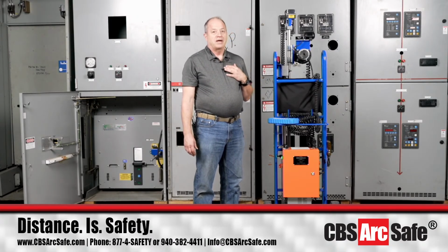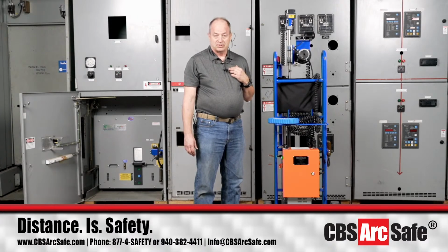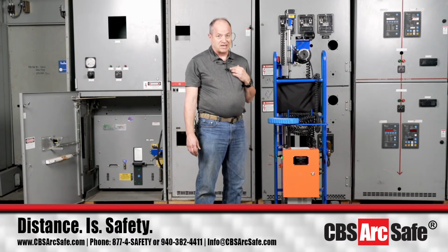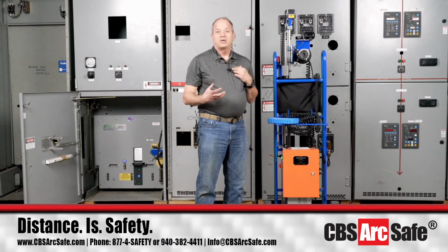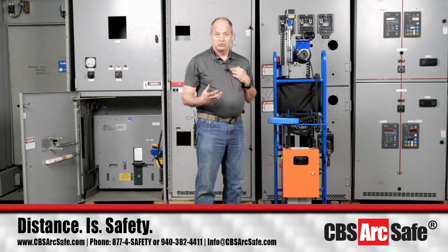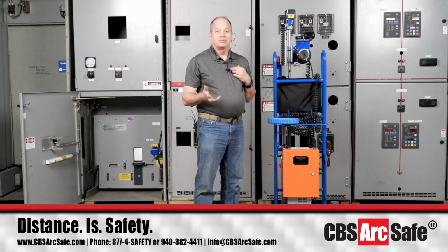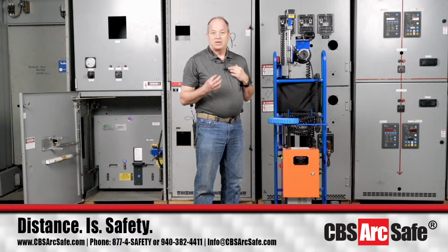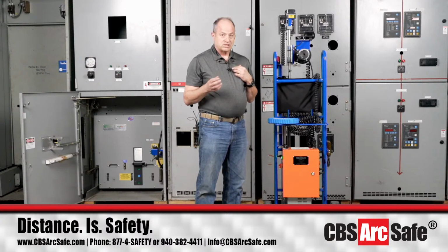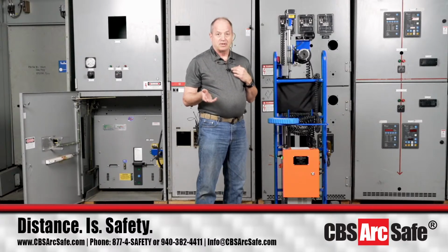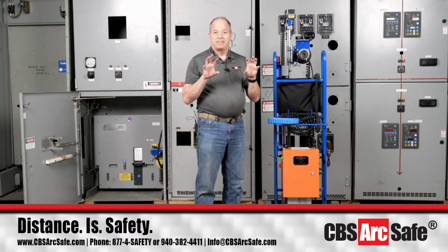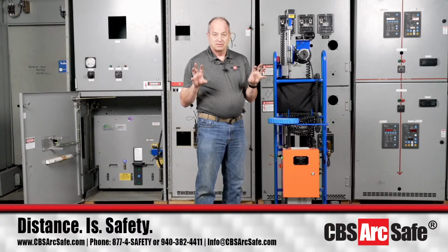Now, I'm not a cubicle diagnostician, so I'm not the guy who can tell you exactly what's wrong. The RRS-1 helps you look at and determine that you do have a problem, and then you get a qualified person to come in, because with older facilities you can have settling foundations, worn racking mechanisms, bent racking mechanisms, and dirty finger clusters where people have mixed various bases of grease. And now if you've got like rosettes, they don't open, they behave like concrete.